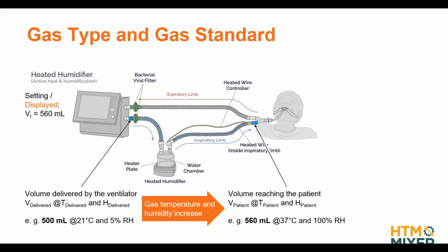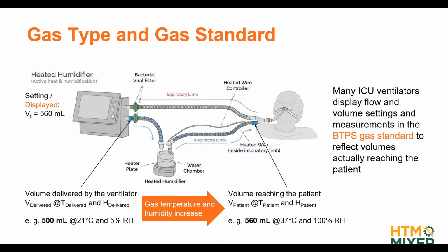So this situation is very typical for ICU ventilators, because 37 degrees, as I already mentioned, and 100% humidification is typically what we want to have on the patient side. This is also called body temperature and pressure saturated. So the gas standard that many ventilators are using is called BTPS. I'm pretty sure you've heard about that, right? That stands for body temperature, pressure saturated. Okay? Does that make sense so far?